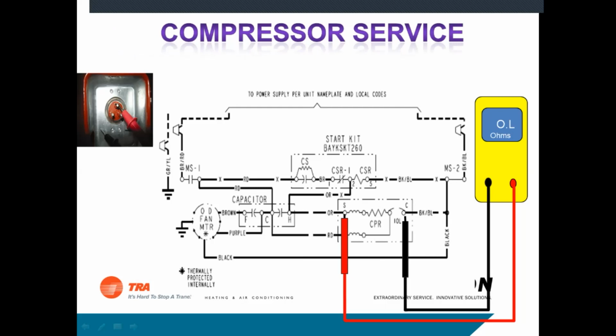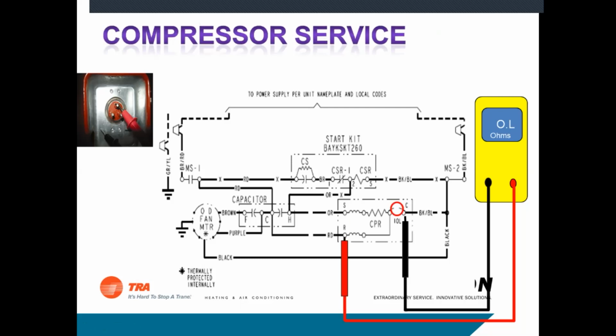If I go from start to common and I see OL, that means either my thermal limit is open or my start winding is open, one of the two. But we're definitely not getting a reading through here, so it could be either one of those. Same thing here. If I go from run to common, it could be my thermal is open, or it could be one of my windings is open. It could be my run winding open at that point. We really don't know which it is.